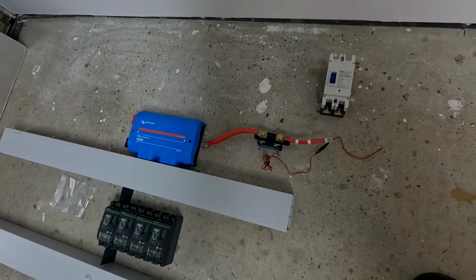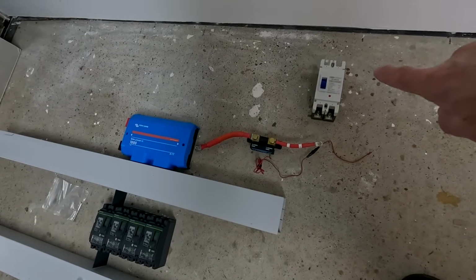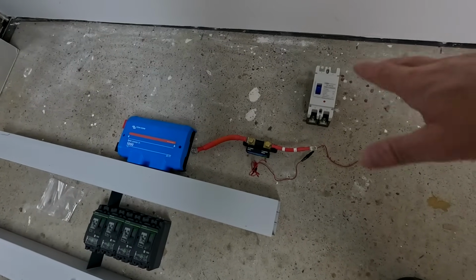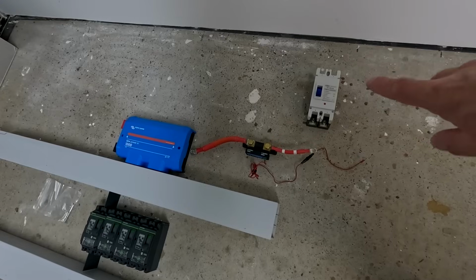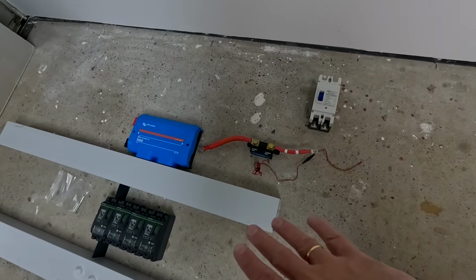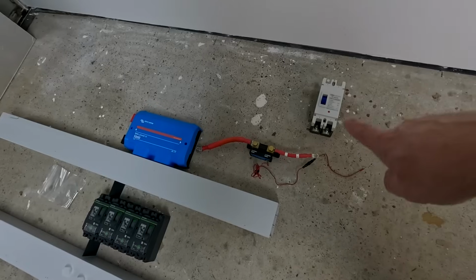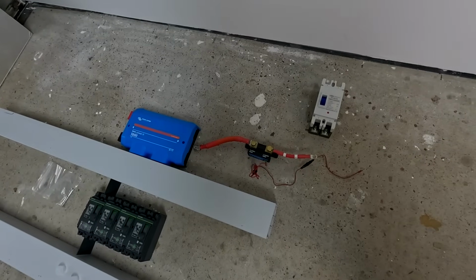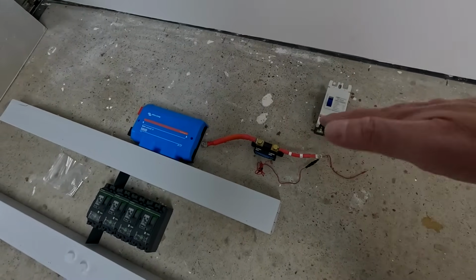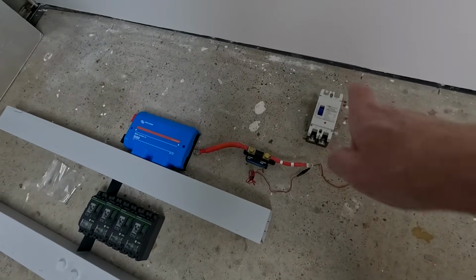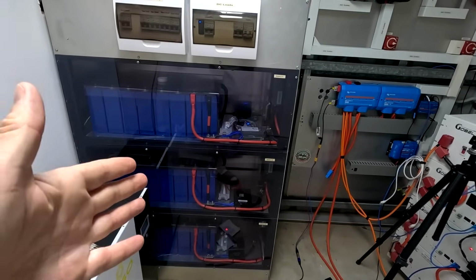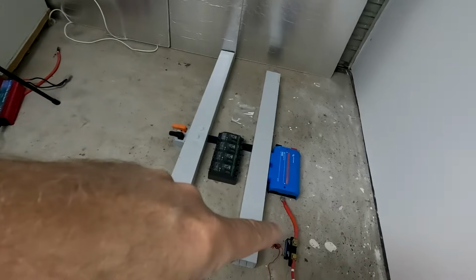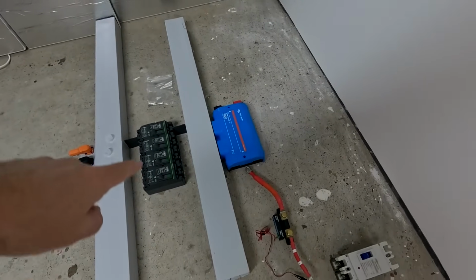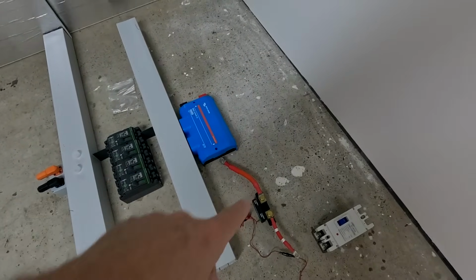Here you can see how it will look. We'll have another bigger circuit breaker, 250 or 300 amps, to isolate all the batteries at once. Right underneath is the Smart Shunt from Victron, which measures all the power going into and out of the batteries. The battery shelf is no exception, so this needs to be connected on the same side as all the other batteries relative to the shunt. Either way, we'll have a cross connection from one side to the other.